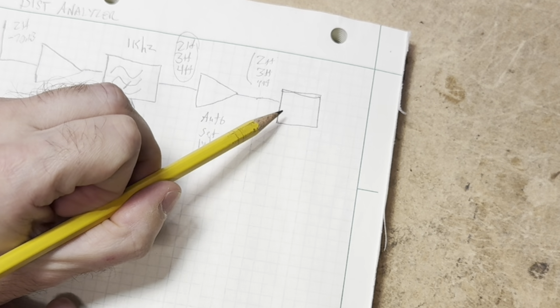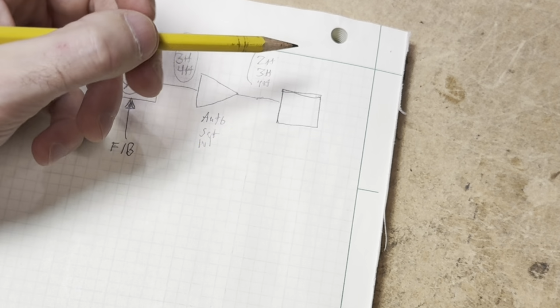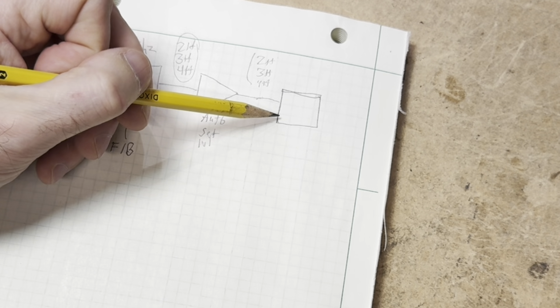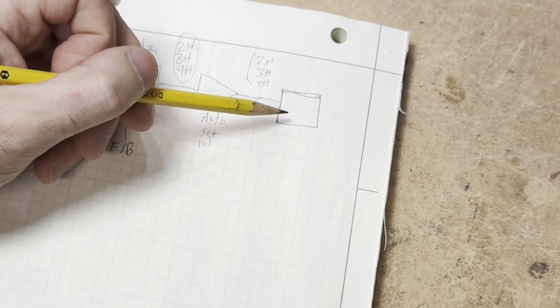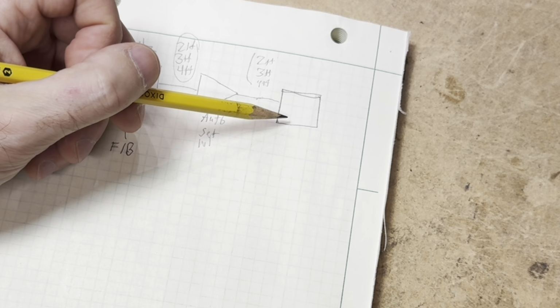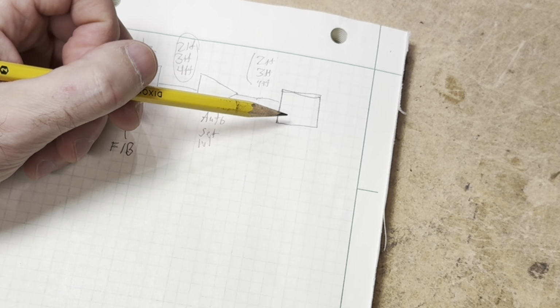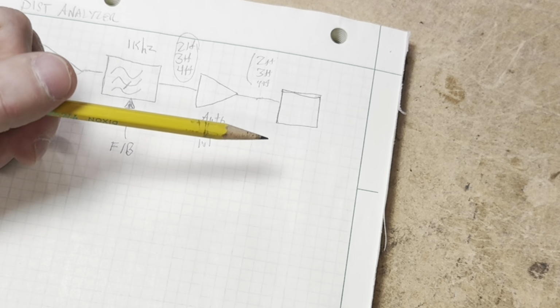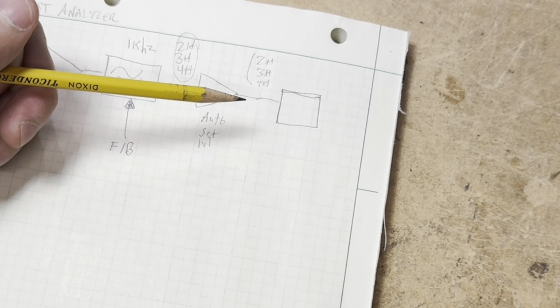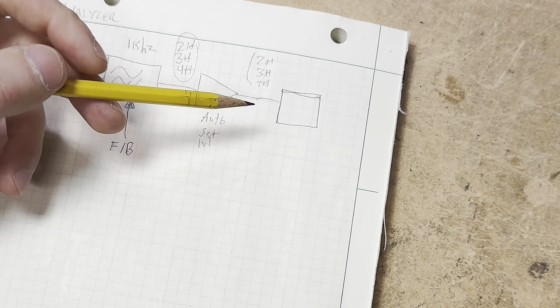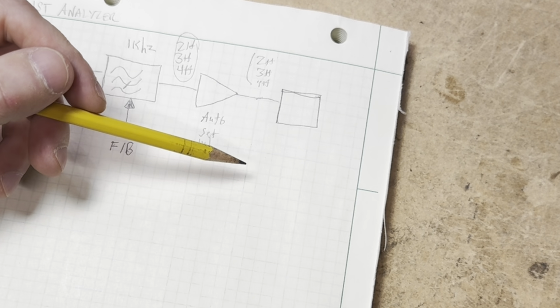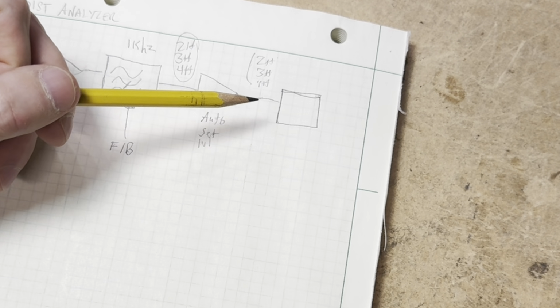What we're going to do here is this is where we'll have our various filters that we can select. On the HP334A unit, there's not a lot of filtering options. There's one high-pass filter that can be switched in that will attenuate products below 1 kilohertz.